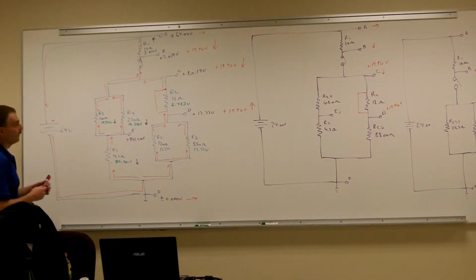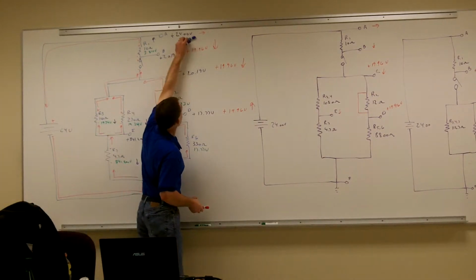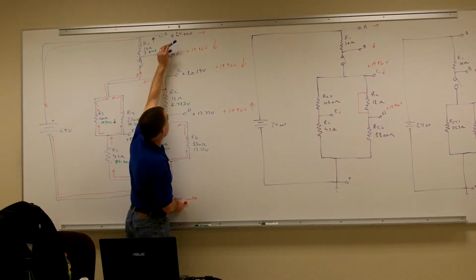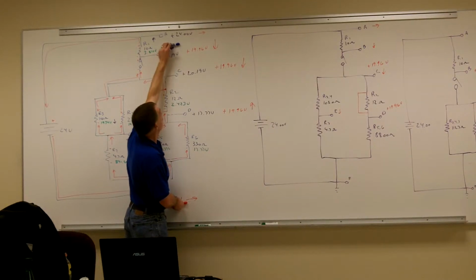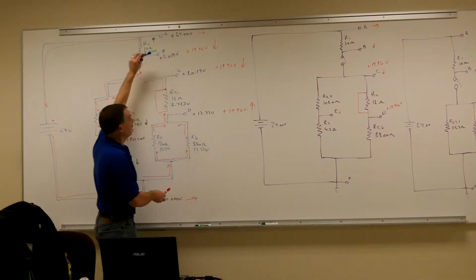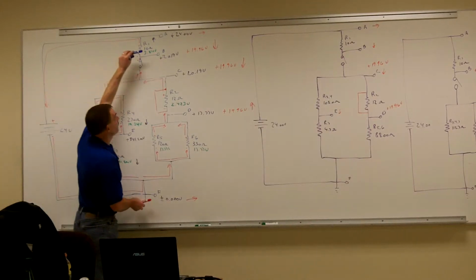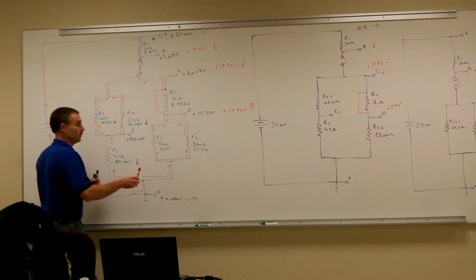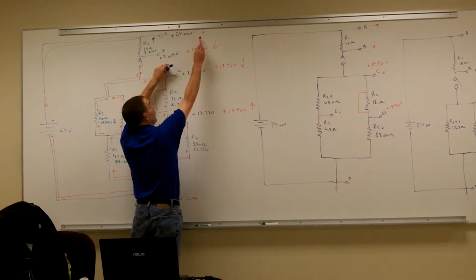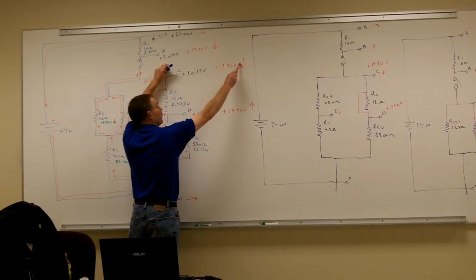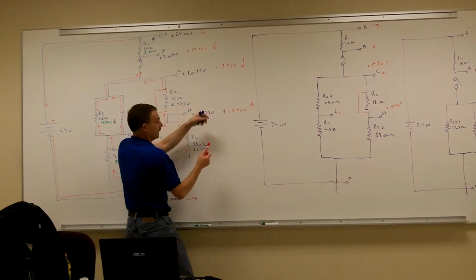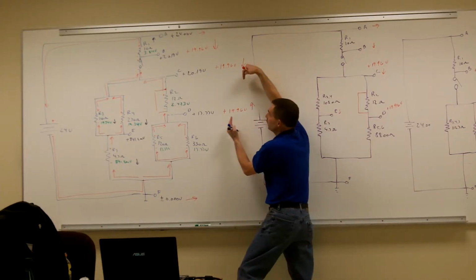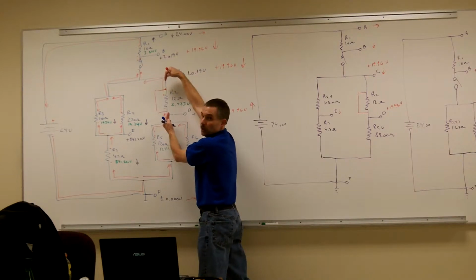What you can do is watch the arrow. Since test points A and F remain the same, I know nothing happened to my source voltage. So then I know that something inside my circuit had to go wrong. If I look at my arrows, as I look down through my circuit, this one went down, and this one went up. And you can see that the direction of these two arrows are actually facing toward the problem, the trouble.